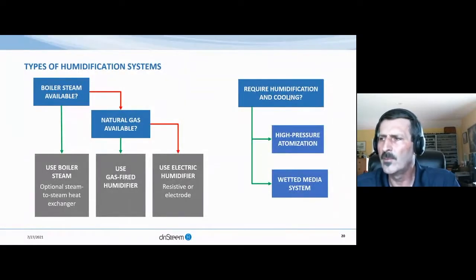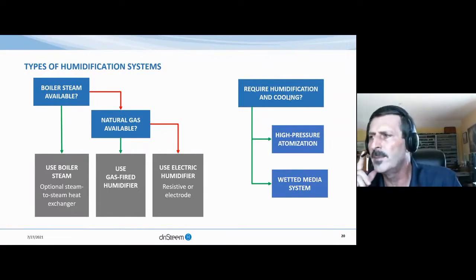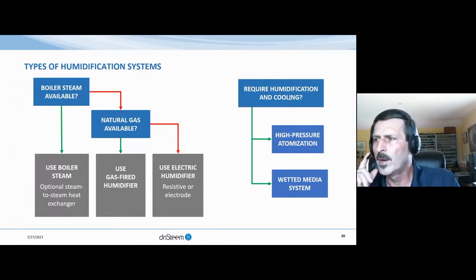Let's take a very high-level look at some equipment choices. On the left, you will see isothermal options or steam-based solutions. If you have boiler or process steam available, that may be your first option. Please note that if this is straight boiler steam that may be treated, you should consider using a steam exchange solution to boil clean water to avoid any boiler chemicals or contaminants in the atmosphere. If you have natural gas available, a gas-fired unit may be your next best option for a lower overall energy cost and the possibility for high capacities.